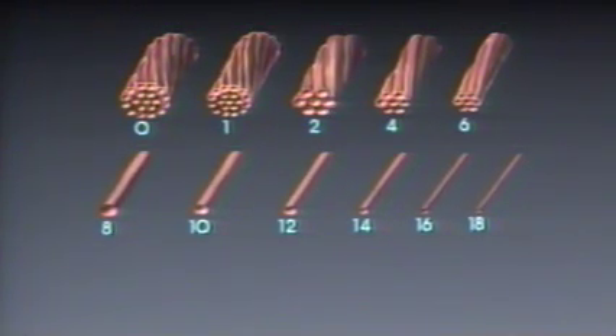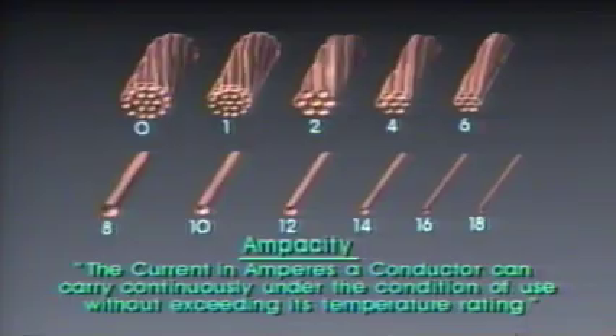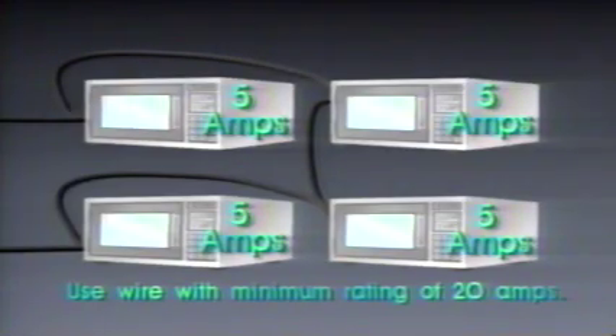Electrical wire is rated for ampacity, or the amount of current that can flow through the wire. This is determined by the wire size or number. According to the NEC, ampacity means the current in amperes a conductor can carry continuously under the conditions of use without exceeding its temperature rating. In other words, if you were supplying power for four 5-amp appliances, the wire must have a minimum rating of 20 amps.